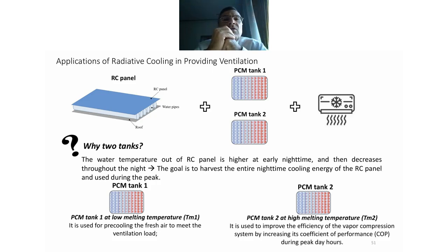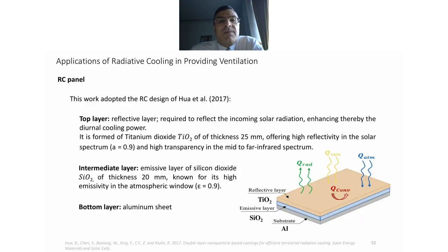The one mentioned by Dr. Surur, we could afford 28 to 30 degrees C going over the condenser, and the ventilation we bring it all the way down to 24 degrees C. That's why we need 2 different PCMs. So tank 1's PCM will have a low melting temperature because we need it at a lower temperature. We could design it with a different material, with different melting temperatures, a lower melting temperature than PCM 2. And PCM 2 is used only to improve the COP of the vapor compression cycle.